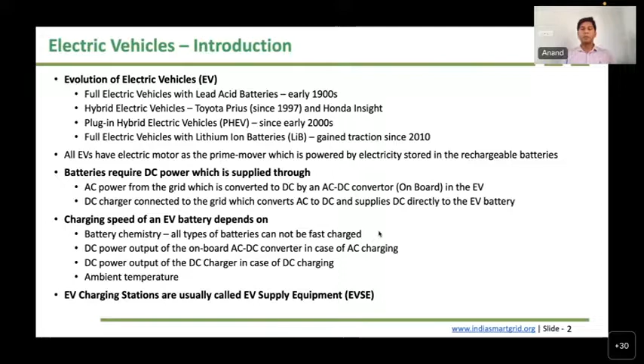Now coming back to the grid, how electric vehicles are impacting it. EVs are usually plugged into the low voltage side of the distribution grid, and there is a huge impact. If it's a small number, it's like any other additional appliance connected to the grid, such as a geyser, drawing around 2 to 3 kilowatts. But if it's huge in number and bigger in size, with chargers at 9, 10, 15, 25, or 50 kilowatts, this is going to make a huge impact on the grid.